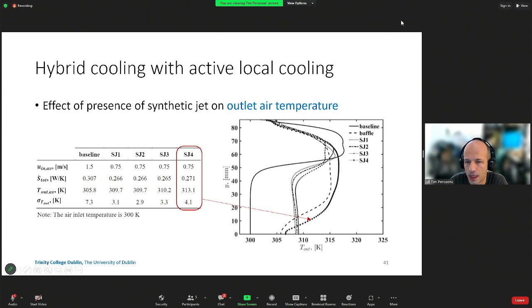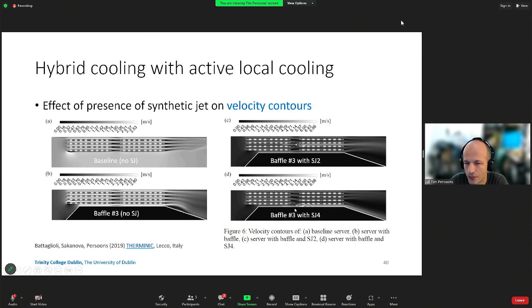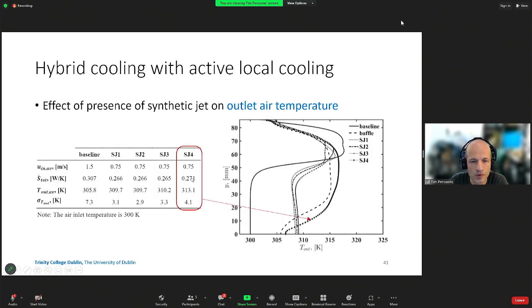Then the effects, for instance, on the outlet air temperature here. From the baseline temperature profile, we can see that we're able to improve the performance quite a bit. If you look at the average outlet temperature from the baseline case, by placing a synthetic jet in that fourth location, so if I go back here, that's this location, in fact, this proved to be most effective in our case because it also helps make the flow more uniform by having this kind of Coanda effect, if you will, downstream of the baffle here. So we're able to get a good improvement of the average temperature at the outlets.